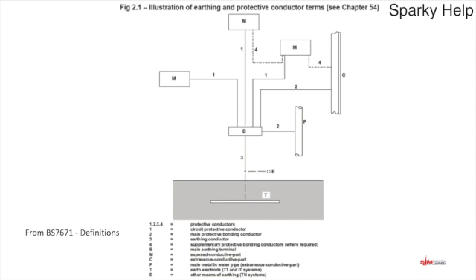So the earthing conductor is the one that goes to your source earth, which in a TN-C-S will come from the neutral link, in a TN-S will come from the sheath of the cable, and in a TT will go to your local earth electrode. Obviously, if we remove the earthing conductor, you will lose the earth to your building, so never remove this before turning the power off. The size of the earthing conductor will vary, and this will vary based on the incoming size of your supply in most cases, but we will look at what they happen to be.